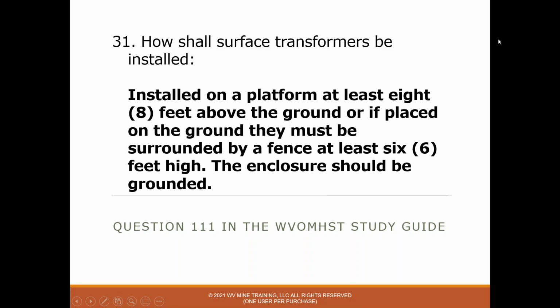31. How shall surface transformers be installed? And the answer is installed on a platform at least 8 feet above the ground, or if placed on the ground, they must be surrounded by a fence at least 6 feet high. The enclosure should be grounded.